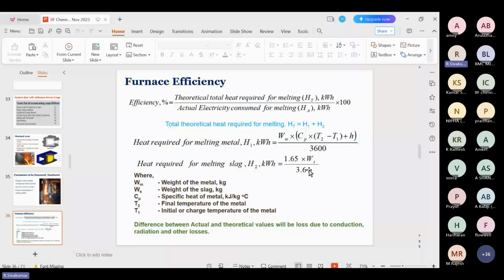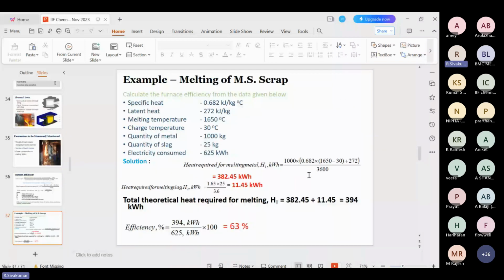Let's see one example: melting of scrap for 1 ton. The quantity of metal is 1 ton. The slag quantity is 25 kg. The specific heat of the metal is 0.682 kilojoules per kg. The latent heat of the metal is 272. Latent heat is nothing but how much thermal energy is needed to go from the solid to the liquid stage. The melting temperature is 1650 degrees. The charge temperature is 30 degrees.